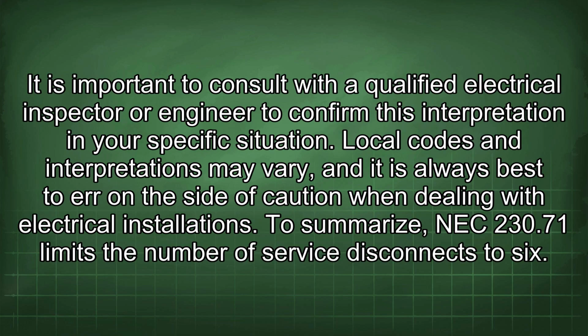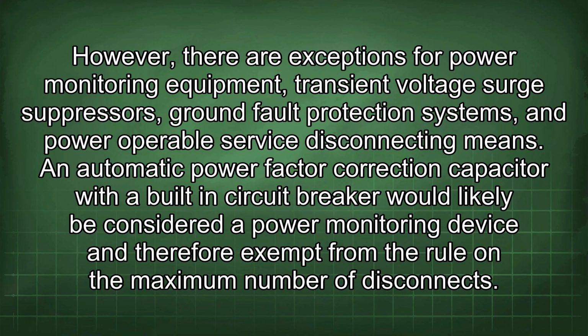It is important to consult with a qualified electrical inspector or engineer to confirm this interpretation in your specific situation. Local codes and interpretations may vary, and it is always best to err on the side of caution when dealing with electrical installations. To summarize, NEC 230.71 limits the number of service disconnects to 6. However, there are exceptions for power monitoring equipment, transient voltage surge suppressors, ground fault protection systems, and power operable service disconnecting means. An automatic power factor correction capacitor with a built-in circuit breaker would likely be considered a power monitoring device and therefore exempt from the rule on the maximum number of disconnects.